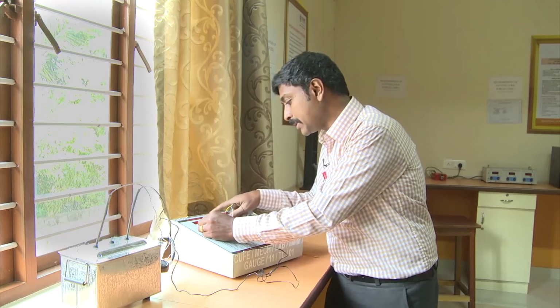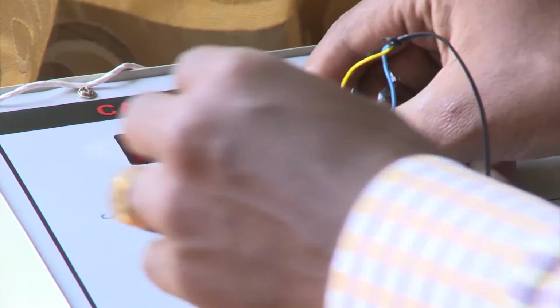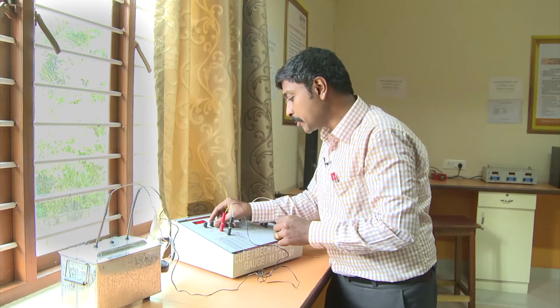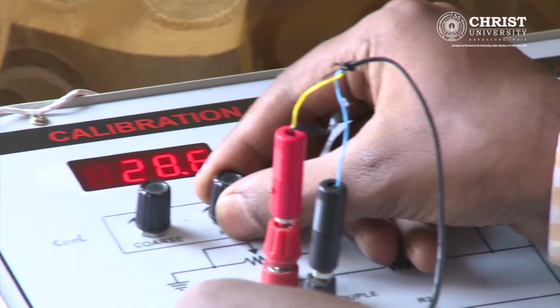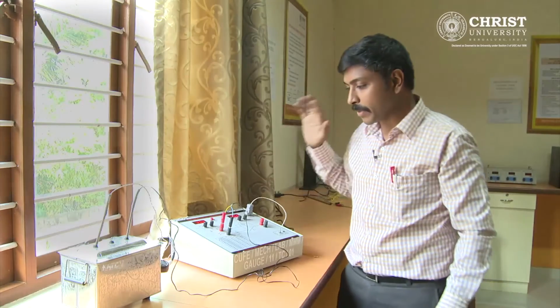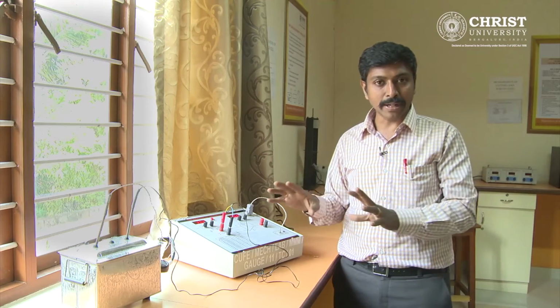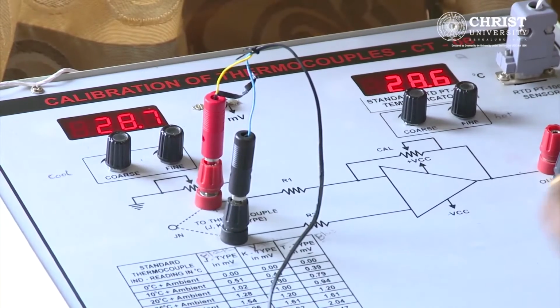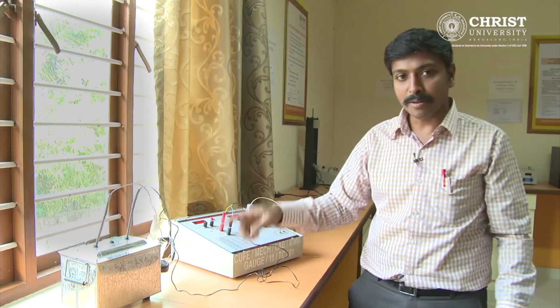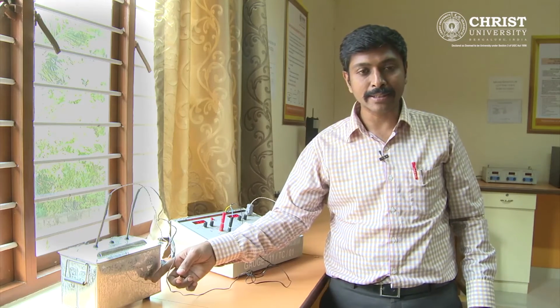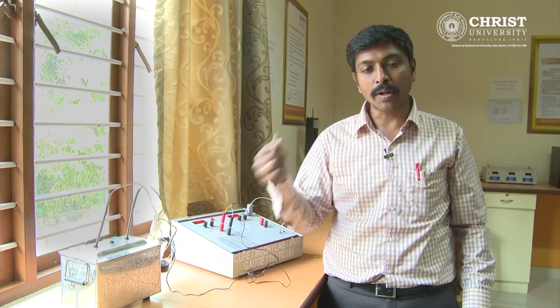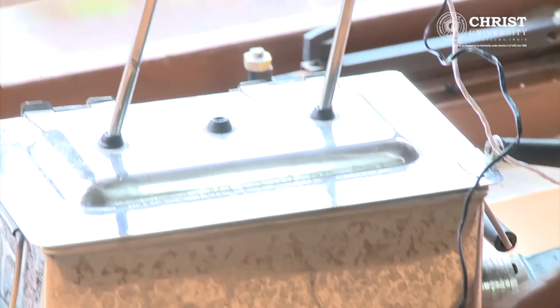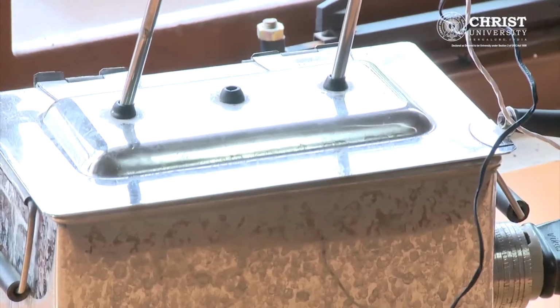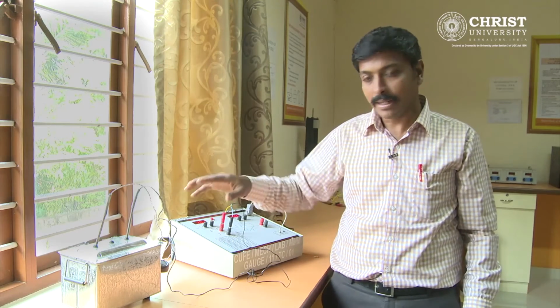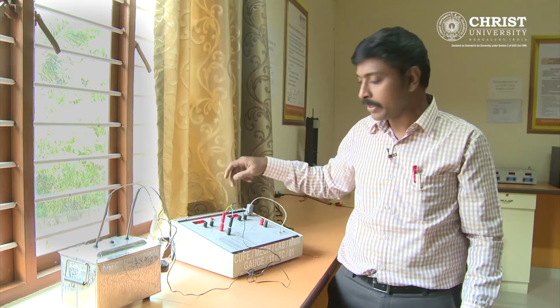It is showing 28.6, this is showing 31, so I am going to change it to 28.6. Now I have altered it and both show 28.6. Yeah, so we kept both in the same equipment. Now, as per our information, both are starting from the same origin point, and the second process is that we have to start the boiler which is kept inside the kettle. It is like a sterilizing kettle which is kept in hospitals for heating syringes. The same kettle we are using here, and a small heating coil will be kept inside. When you excite the temperature, it will increase by every 5 or 10 degrees centigrade, and you have to monitor the change in degrees Celsius on these two displays.